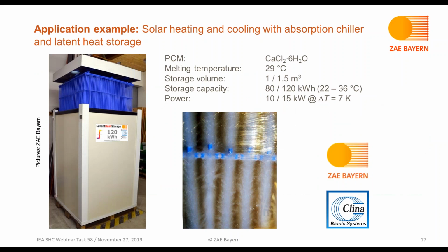On this slide, you see a picture of the storage that has been used in the installation. As I said, the PCM is calcium chloride hexahydrate with a melting temperature of 29 degrees C. There are two types of storages, one with 1 and 1 with 1.5 cubic meter storage volume. And as you can read, the capacity is either 80 or 120 kilowatt hours in the temperature range between 22 to 36 degrees C.